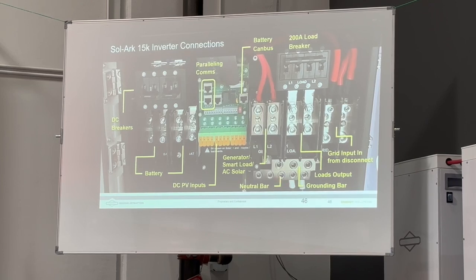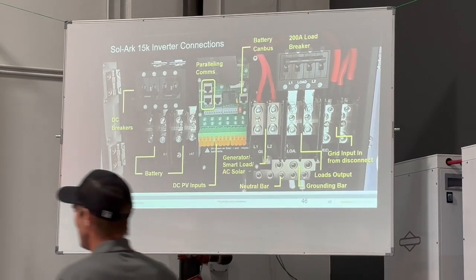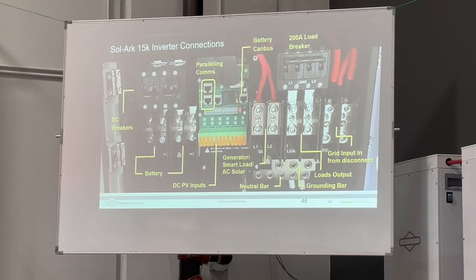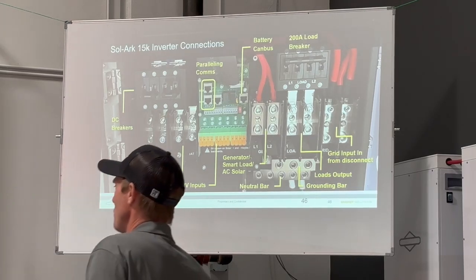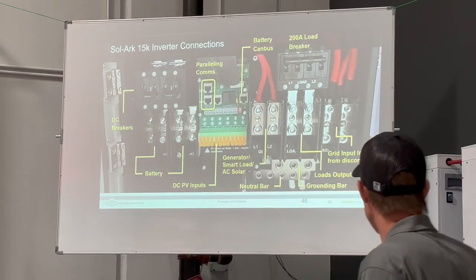If you have any strength within Sol-Ark, I would get you to have them switch the ground bar and the neutral bar. It is a little tight to get your neutral connections down here at the bottom. Otherwise, you've got a lot of space compared to other inverters. But you'll notice once you wire one of these, getting the 3/0 connections, the neutral, bent up and in at the bottom is a bit challenging. Tight fit, but the grounding wire is a little bit smaller, so it's easier to bend. So that's my only recommendation.